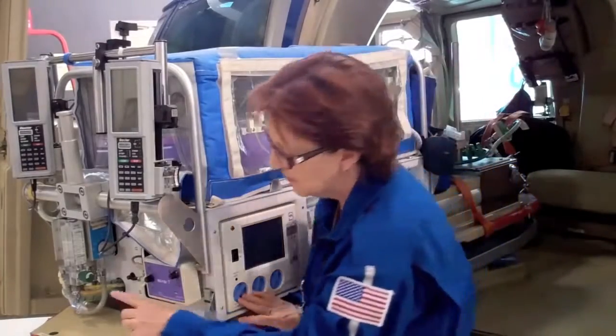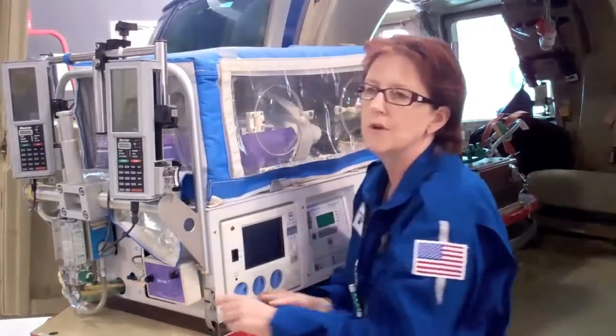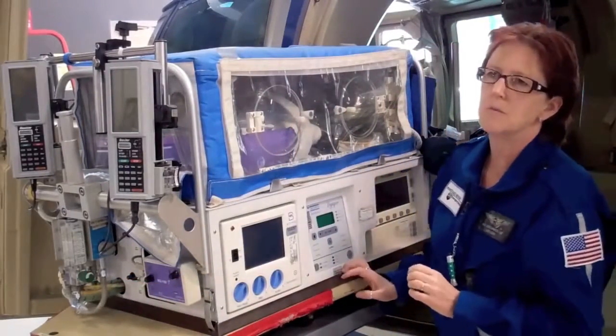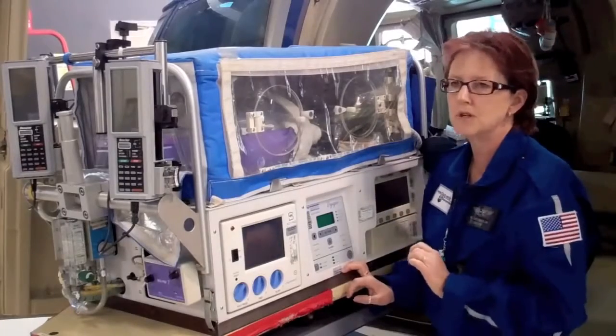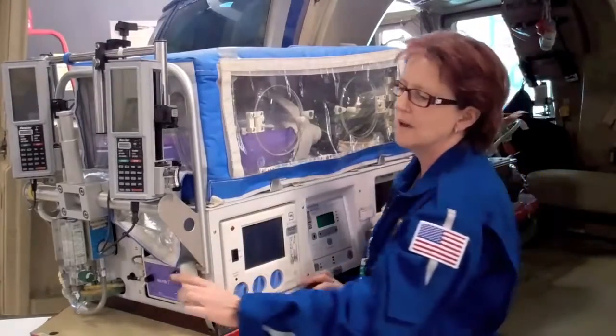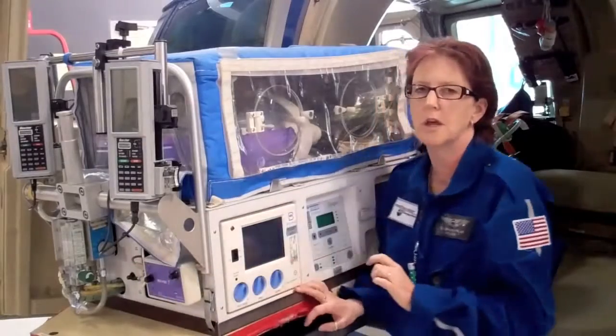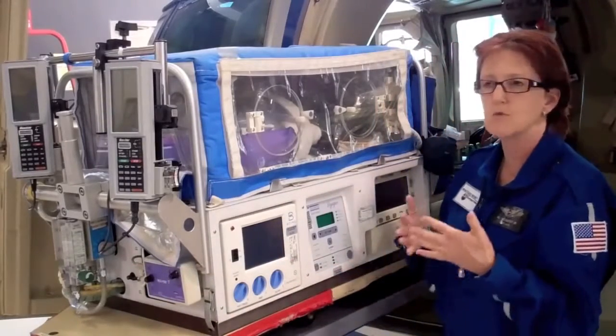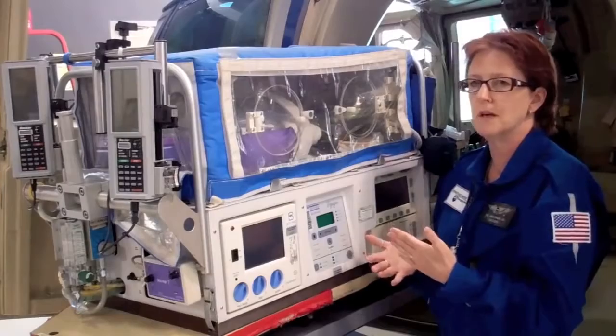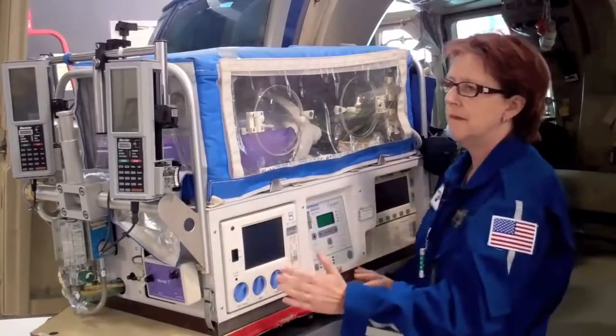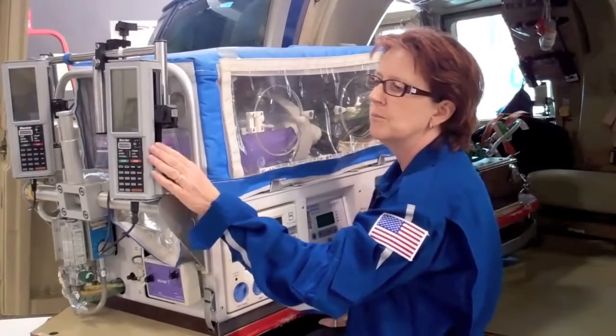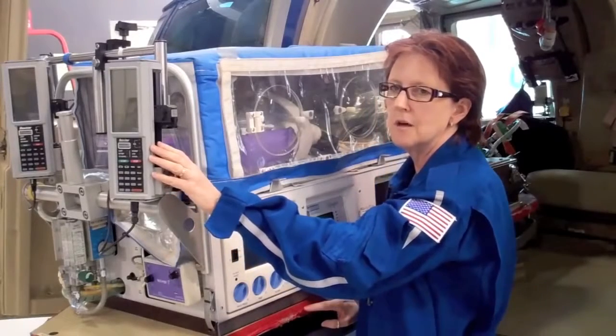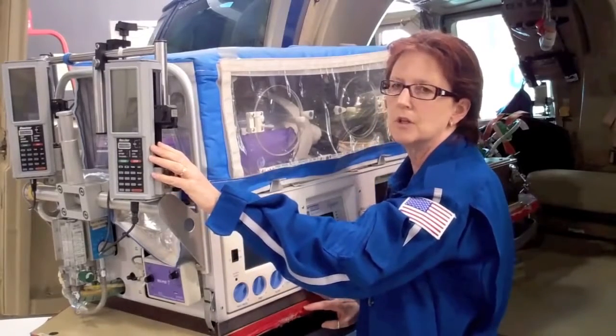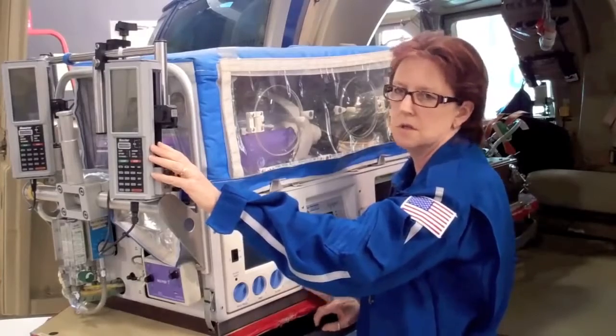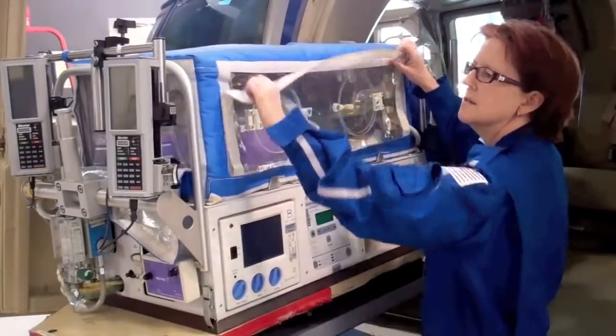On the end of the unit, we have a blender. We carry both air and oxygen. Very premature infants need oxygen, but they don't need too much oxygen. Too much oxygen can be bad. So we can actually set the percentage of oxygen that they're getting anywhere from 21%, which is room air that you and I get, to 100%, which is pure oxygen. We set that. We also carry syringe pumps so that if they need IV medication, we can regulate that very closely down to 1/10 of a cc an hour.